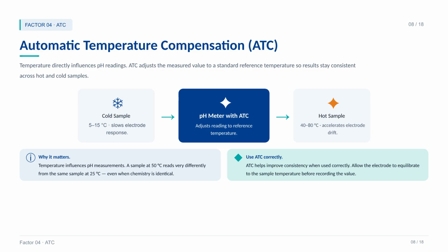Simple as that. Factor 4, automatic temperature compensation, or ATC. Here's something people forget. Temperature directly affects pH readings. The same sample measured at 5 degrees and at 50 degrees will give very different values, even though the chemistry hasn't changed. ATC adjusts the reading to a standard reference temperature, so your results stay consistent across hot and cold samples. But remember, let the electrode equilibrate to the sample temperature before recording. ATC helps, but it's not magic. Used wrong, it gives you a confidently wrong number.